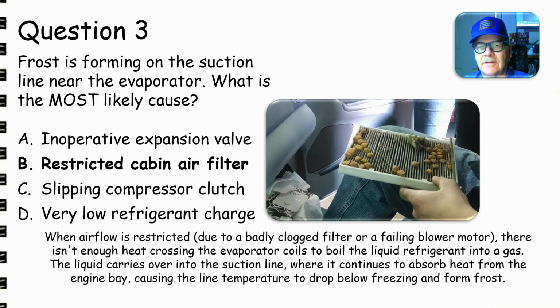Usually if you have frost forming on that suction line, that means a problem. Most of us won't go chasing that problem unless there's also another problem, like the evaporator freezing up or something like that. You can be a stickler and work on something that's not broke just because you don't like the frost on the suction line, but sometimes because of humidity and other factors, you're going to see frost on the suction line.